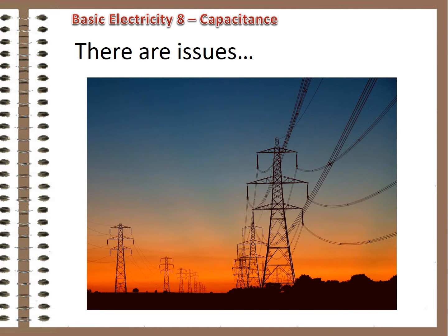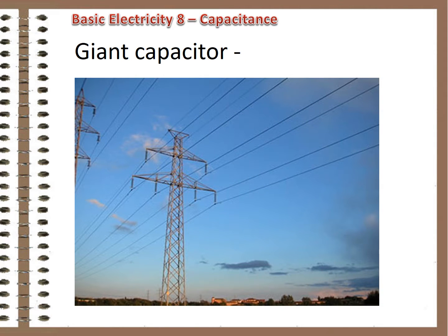That's all fine, but there are sources of capacitance in a circuit that can cause problems. Power lines running next to each other constitute charges separated by a dielectric — the air in this case — which makes a capacitor. A long, lightly loaded transmission line is essentially a giant capacitor wired into the electric system.